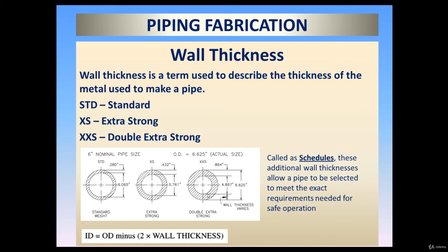For example, for this 6-inch pipe, the OD is 6.625. Here you can see in the standard, the thickness is 0.280. This is the wall thickness. For XS, the wall thickness is 0.432. For double XS, that is double extra strong, the wall thickness is 0.864. The outside diameter is constant and the ID is getting changed. For finding out ID, it is OD minus 2 into wall thickness. 2 wall thickness has to be subtracted from the OD to find this ID.